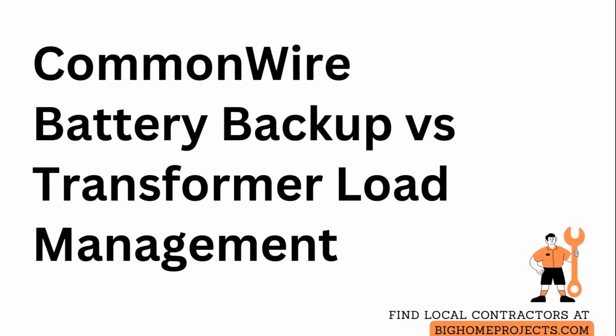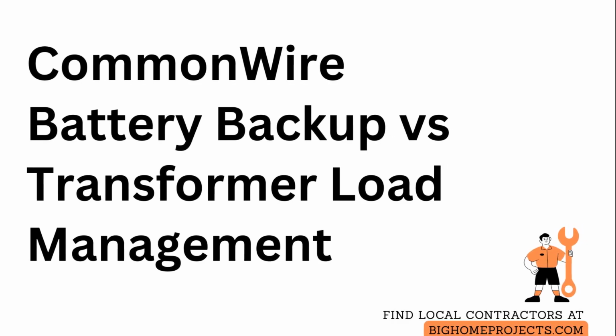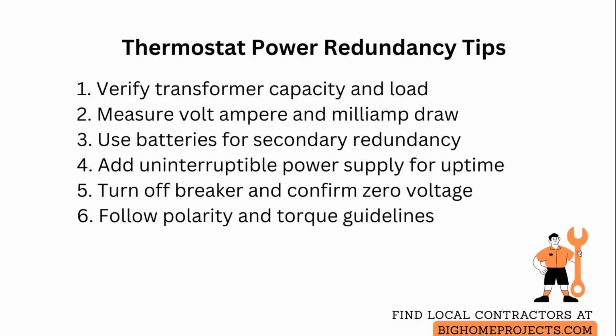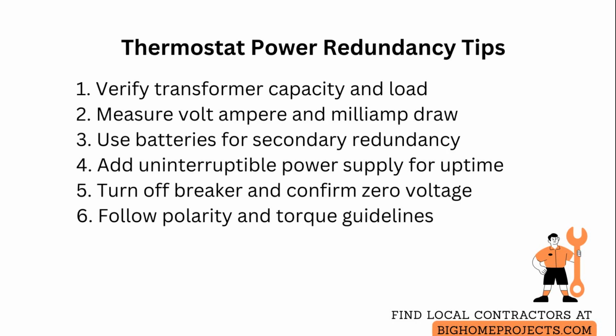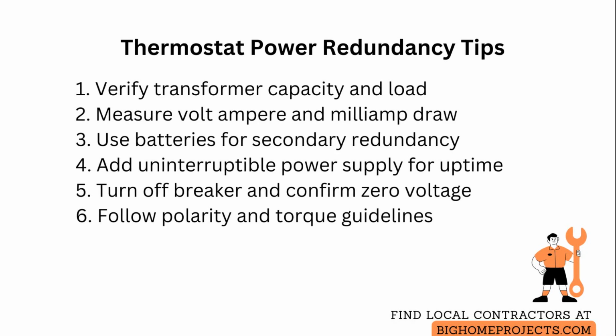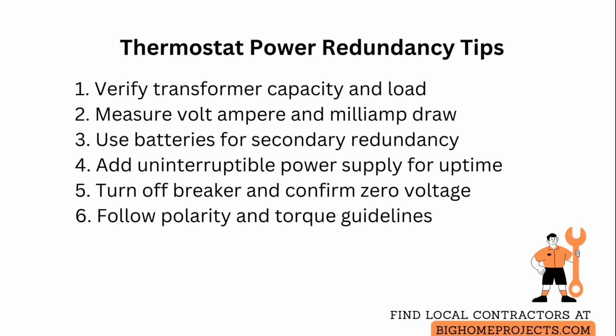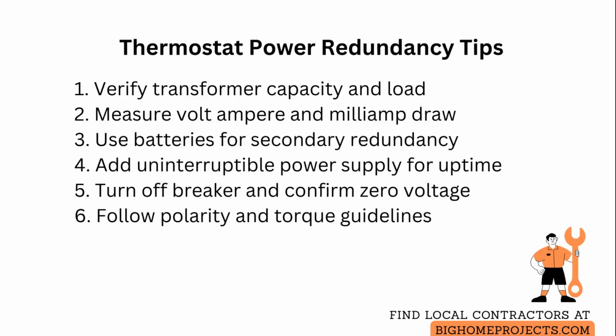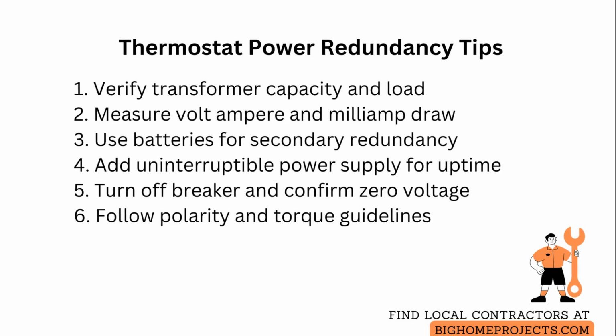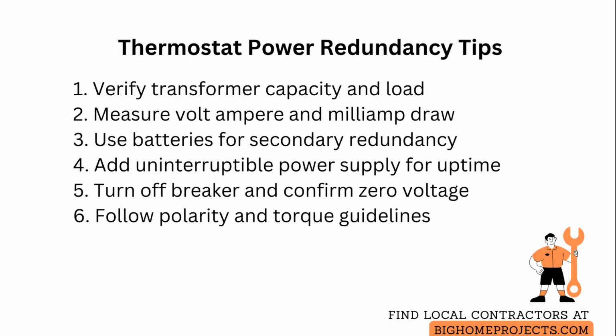Do batteries need to be installed if a common wire is used for power redundancy? When a thermostat or device has a common wire providing continuous 24-volt power from the heating, ventilation, and air conditioning control board, batteries are not strictly required for normal operation because the common wire supplies the steady current the device needs. However, it is best practice to verify the transformer capacity and the total current draw of all connected devices so the circuit is not overloaded.